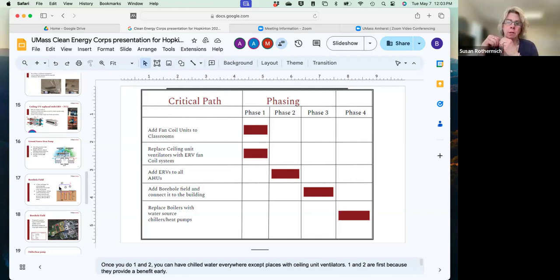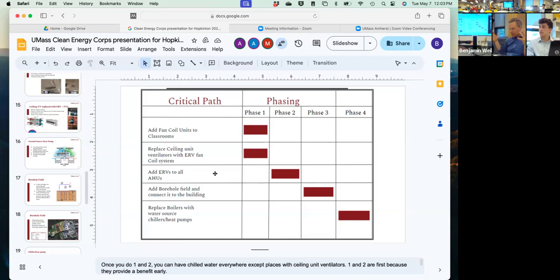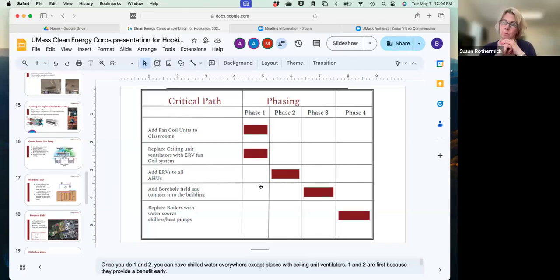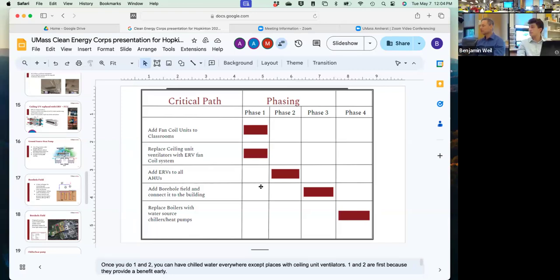So phase one basically gets cooling efficiently into all our classrooms. Yes. And then phase two gets efficiency to the AHUs, which is, excuse my ignorance, going where throughout the building? So that is all the major spaces, you could think of it as all the major spaces, but the key thing is by doing both of these things, all of phase one and phase two, the new maximum water temperature for the building is 105 degrees instead of 160 degrees. And that is the enabling characteristic that allows you to use a heat pump.